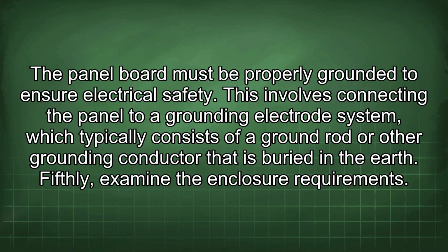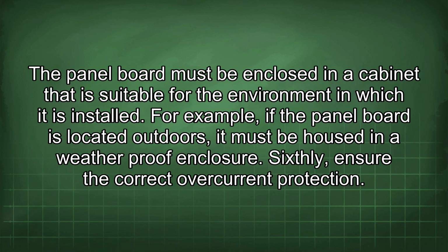Fifthly, examine the enclosure requirements. The panel board must be enclosed in a cabinet that is suitable for the environment in which it is installed. For example, if the panel board is located outdoors, it must be housed in a weatherproof enclosure.